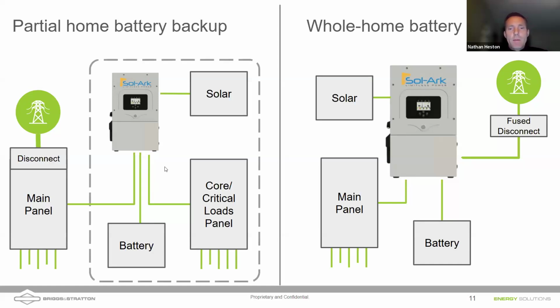In a partial home backup scenario, as this dashed line indicates, the inverter isolates itself from the main panel. We don't want to be energizing the main panel and sending electricity back onto the grid and potentially harming somebody who's working on the lines. And so what we do is we back up just the core critical loads with a partial home system.